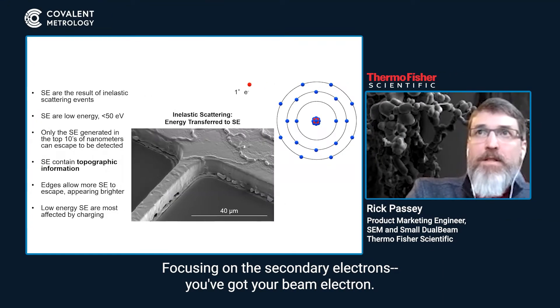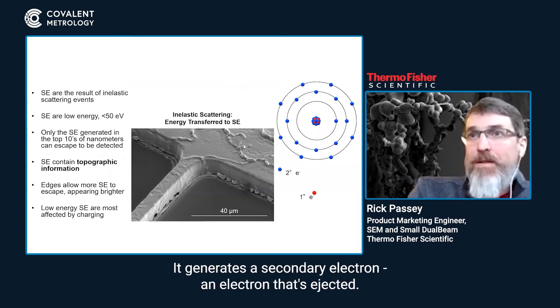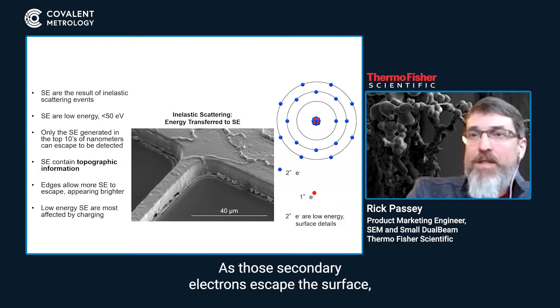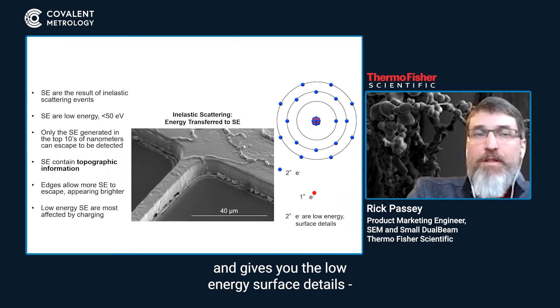Focusing on the secondary electrons: you've got your beam electron - it comes in, interacts with the sample, and generates a secondary electron, an electron that's ejected. Those electrons don't alter the material; they're simply changing places. As those secondary electrons escape the surface, there's a detector that picks up that signal and gives you the low energy surface details - very topographic information.